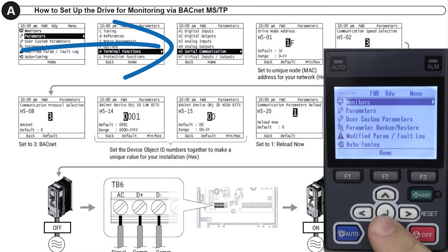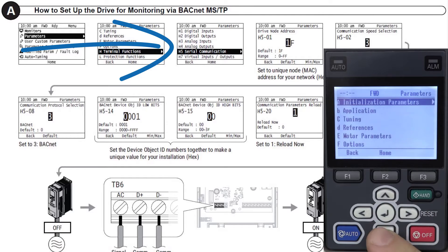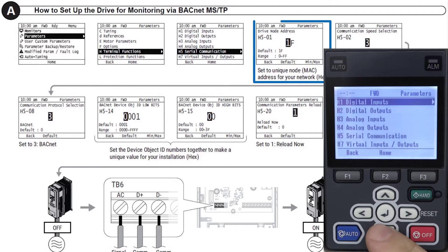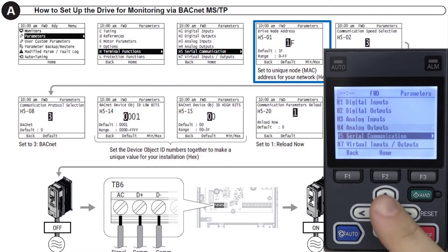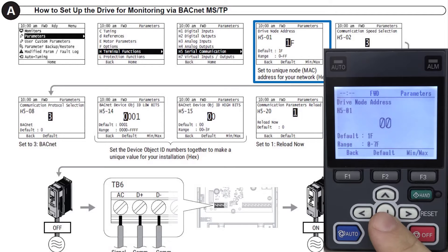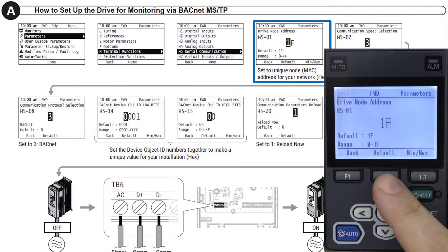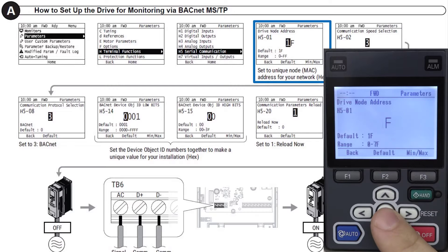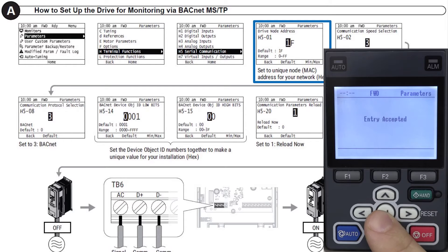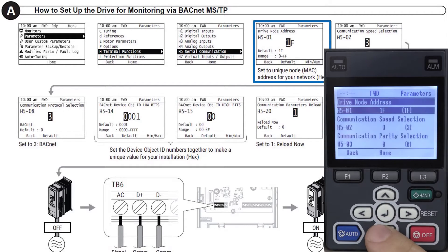First, navigate to the parameter group H5 Serial Communication. Set H5-01 to a unique node address for your local MSTP network. This value is entered via hexadecimal format. After, press Enter to confirm with an entry accepted message.